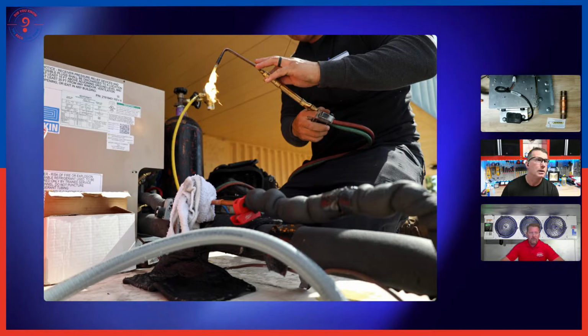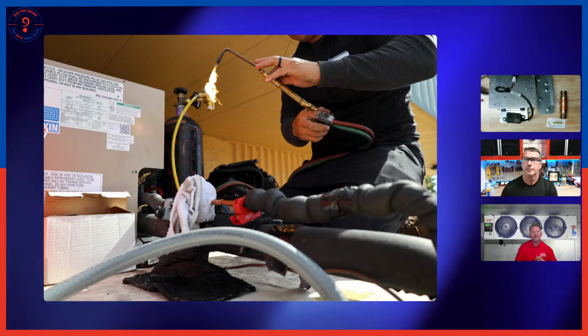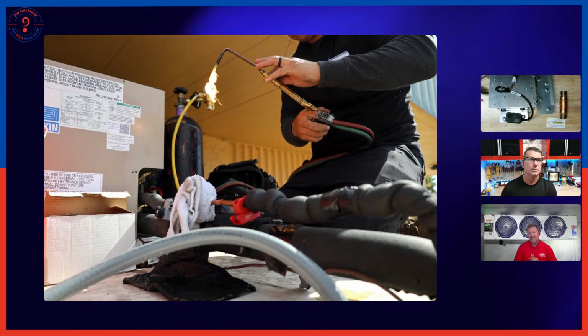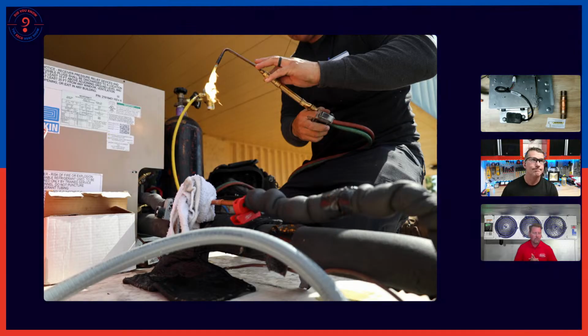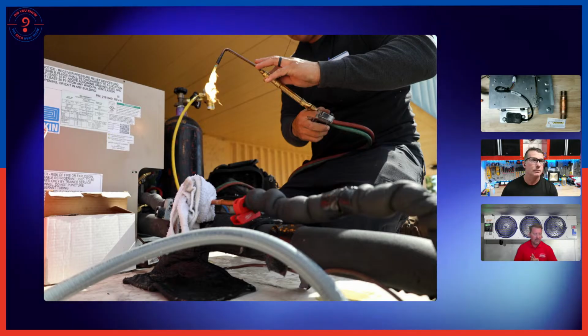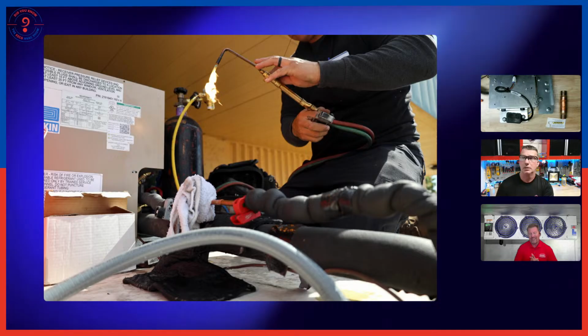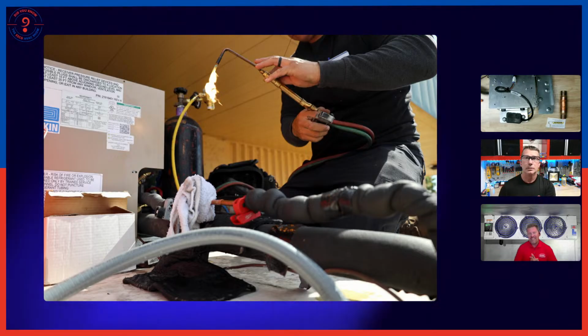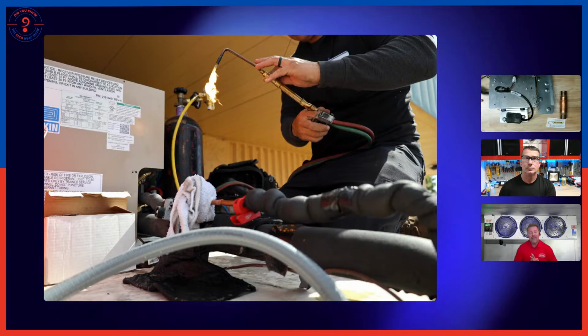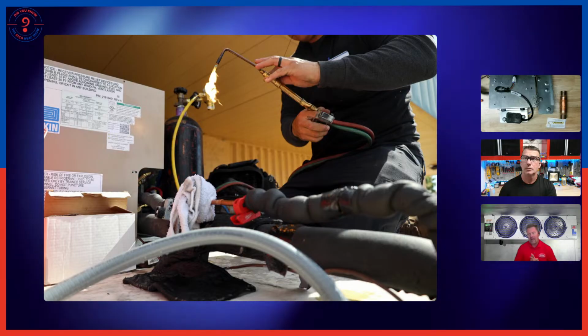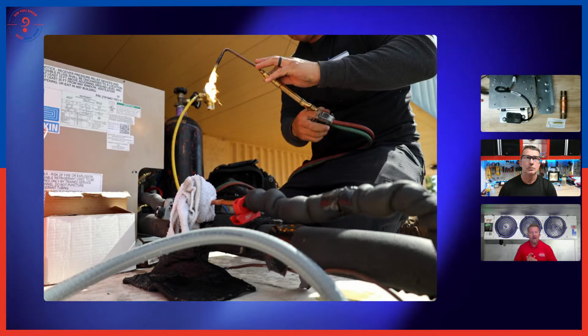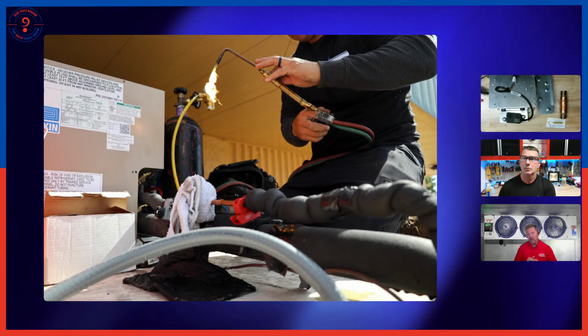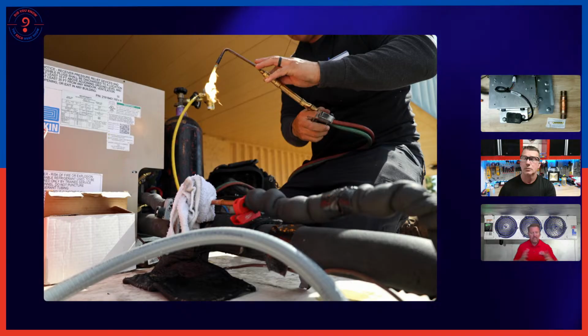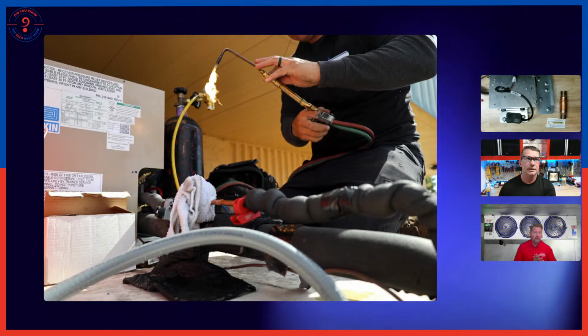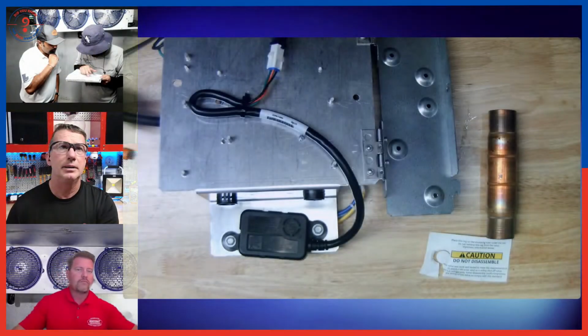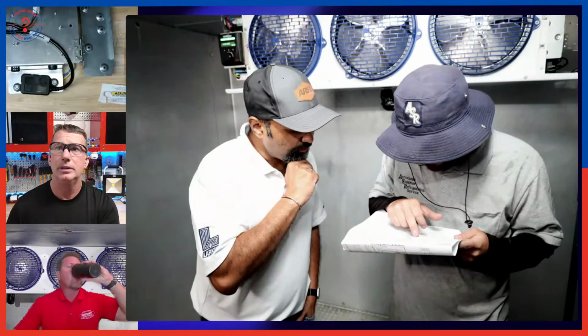But the general consensus and the safest thing is for us to put that solenoid as close to the box as possible, but outside the box. Now, on a short run, it becomes less and less critical. But let's say we have a 150-foot line run. If we put that solenoid near the condenser, we now still have 100 feet of liquid line that potentially could have a partially flammable gas in it. So we want to have that solenoid as close to the walk-in as possible so that we trap the least amount of A2L within the area that we are trying to keep safe, which in this case would be inside the walk-in.